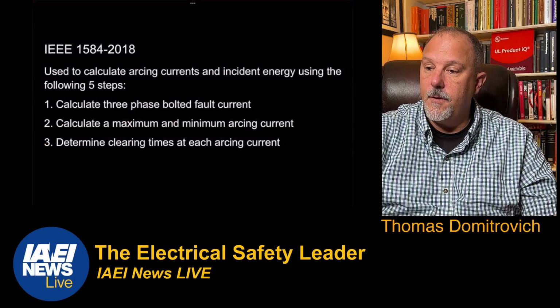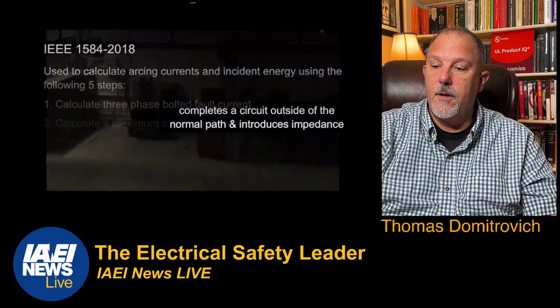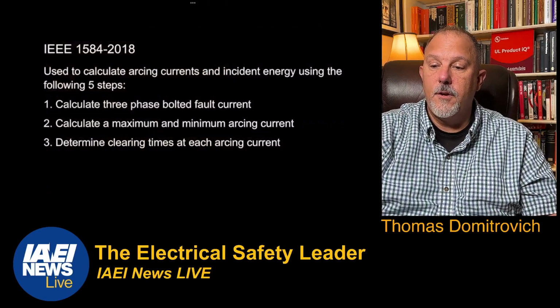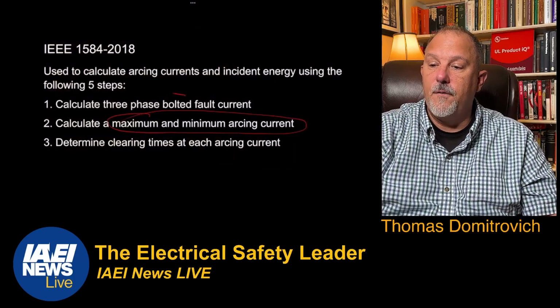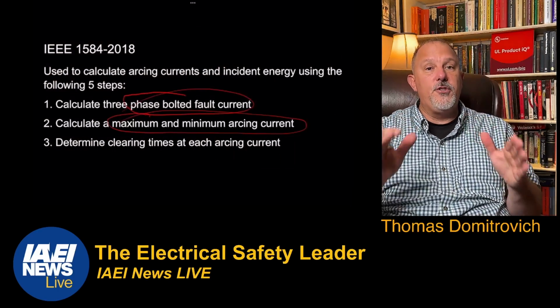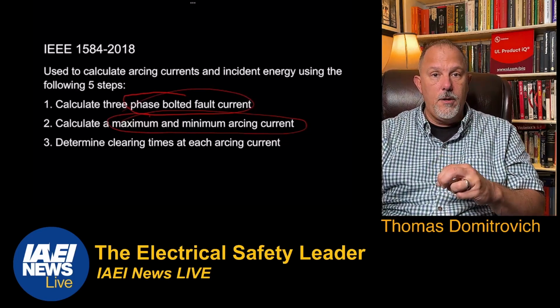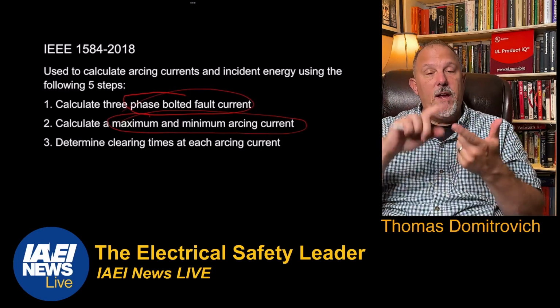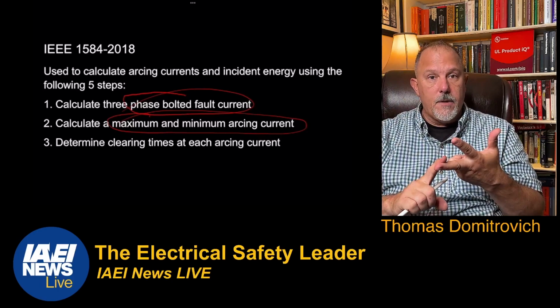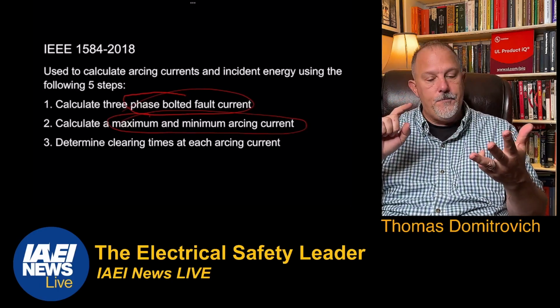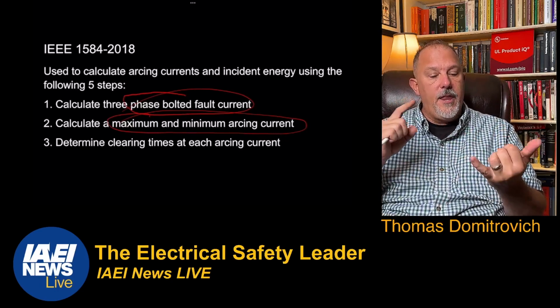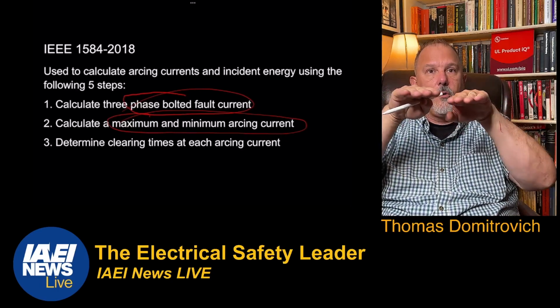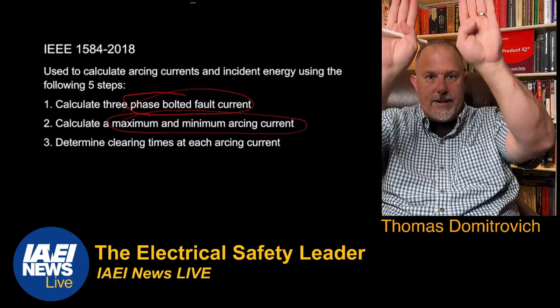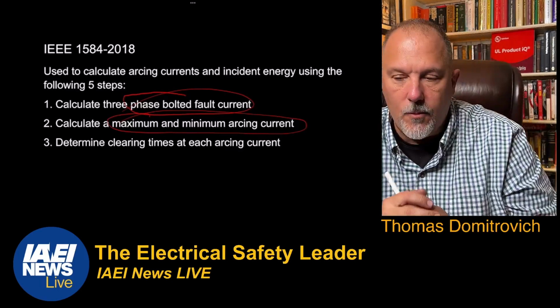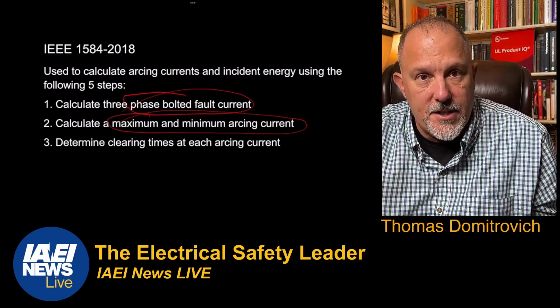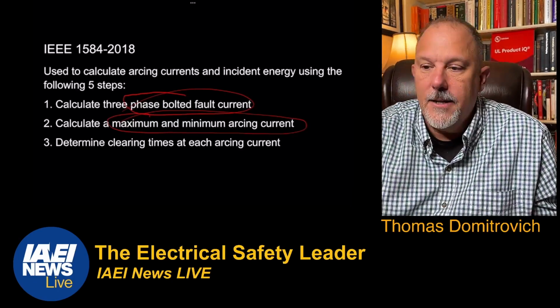So this discussion of calculating the minimum and maximum arcing currents based upon the three-phase bolted fault current, we use the equations that are developed in IEEE 1584 to do that. And those are our parameters. We have the gap in between electrodes. We have the voltage, how much pressure is in the system. We have what the available fault current is. And then we have the electrode configuration, whether it's horizontal, looking at you, or vertical, like in a panel board, up and down. So we have all those parameters, and all of that research gave us the equations to calculate the maximum.